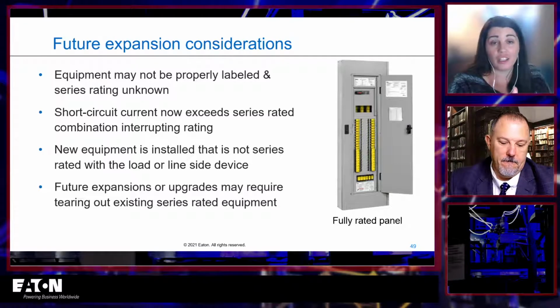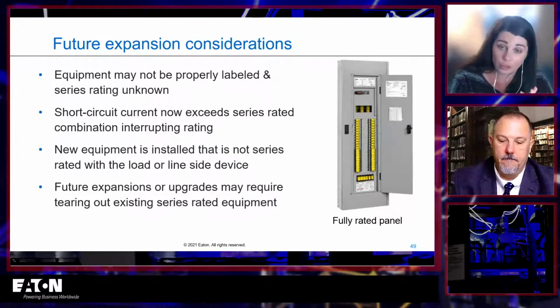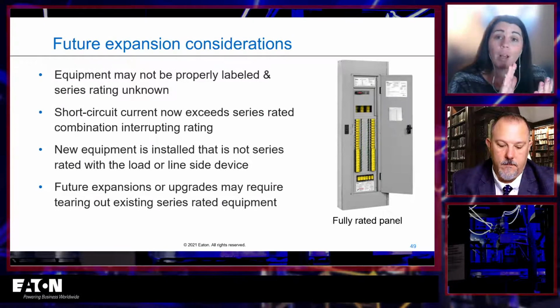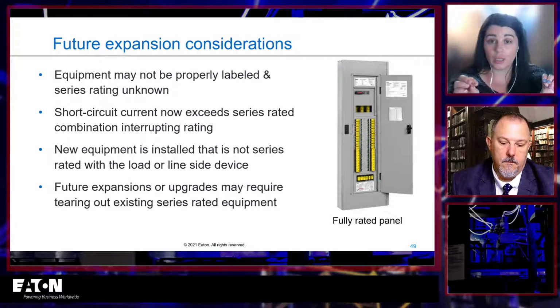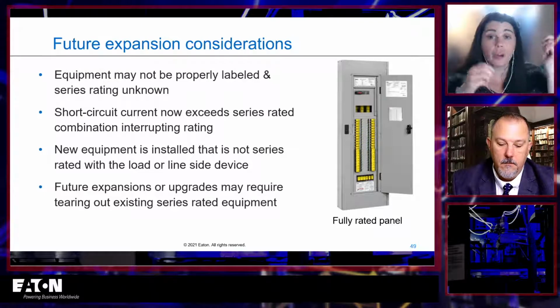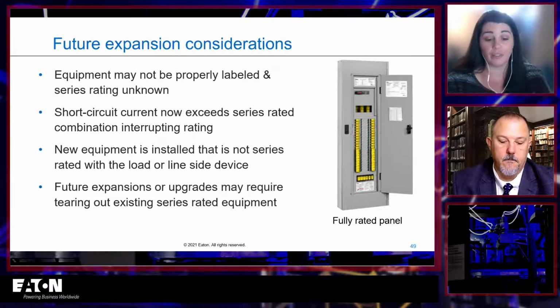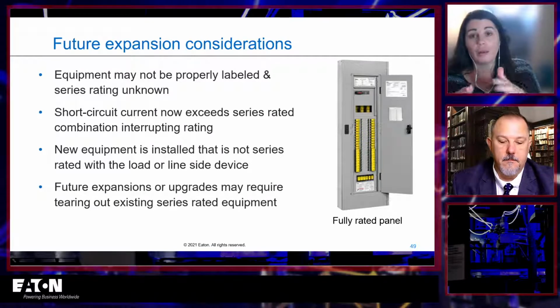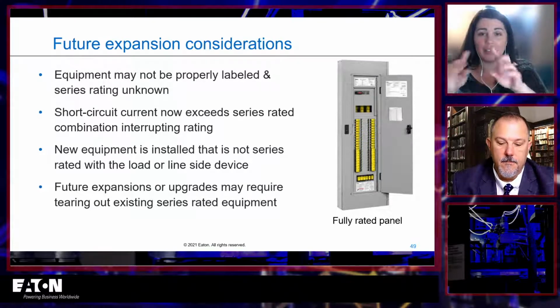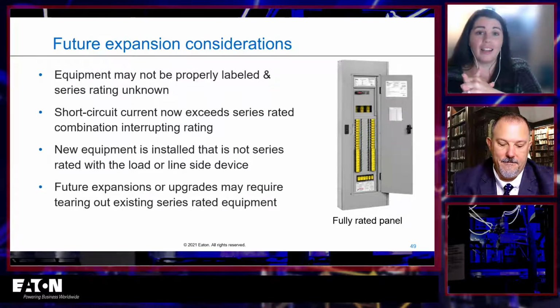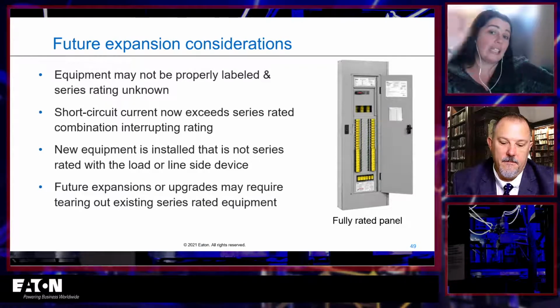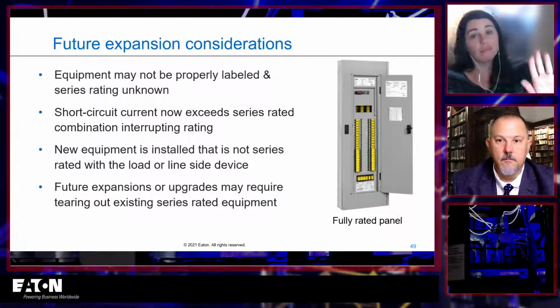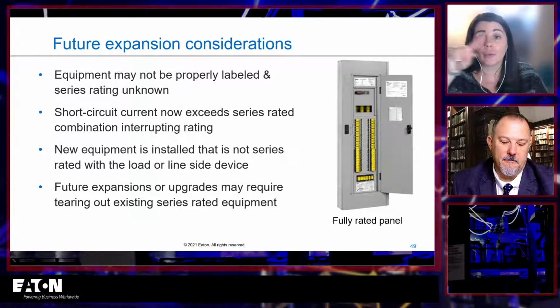But sometimes that isn't in fact what you are doing. When you have insufficient fault current, you are going to find a series rating, and if you do, use a tested combination. And what's interesting is when you look it up, it's typically going to be a series rating with the whole panel board. So there are series ratings of like fuse plus breaker or breaker plus breaker, but a lot of times it's actually, hey, I have an Eaton Pow-R-Line 3 or 3A or however, they do weird things with the letters and numbers. I don't remember what they are anymore. And then it's a fuse plus an Eaton Pow-R-Line 3, 4, whatever. Right. Separate, and you get that combination for the whole thing.